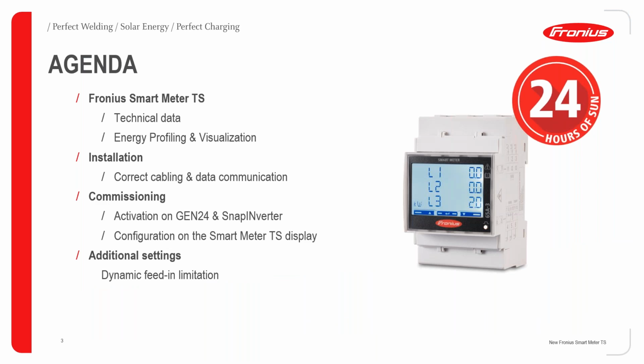So the agenda today is the Fronius Smart Meter TS. We will first look into the technical data, then energy profiling and visualization, then installation: how to cable the smart meter in the correct way, and the data communication of the smart meter to the inverter and to Solar.web. Then the commissioning of the smart meter: how to activate the smart meter in the Gen24 interface page, and also the SnapINverter series interface page. Then configuration of the smart meter in the display, because when it comes to multiple smart meter usage for energy profiling, you need to configure the numbering of the smart meter in the display. Let's see how to do it, and then the additional settings like dynamic feed-in limitation. We'll see in detail.